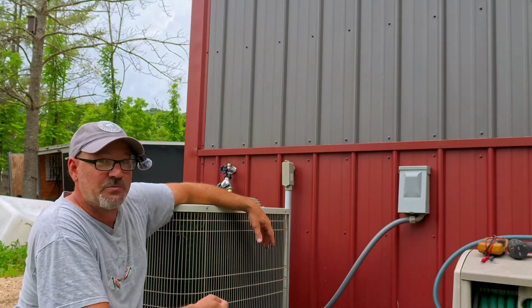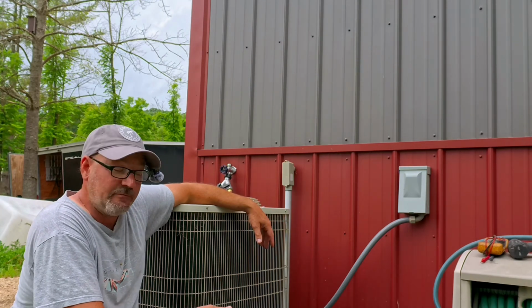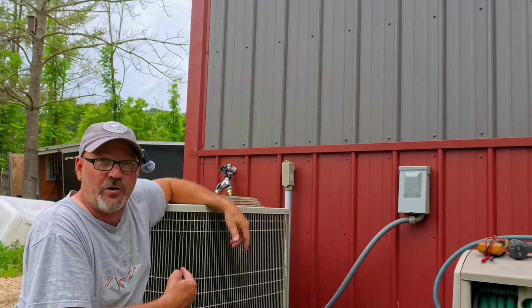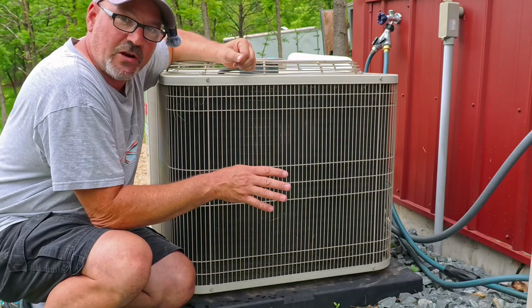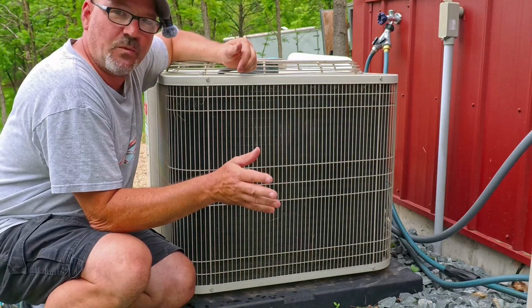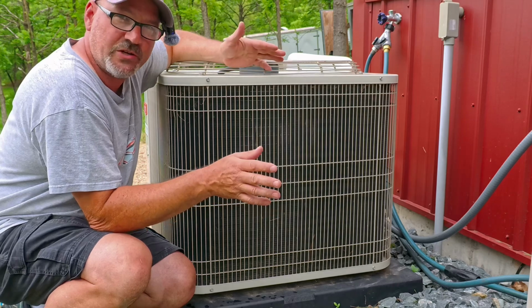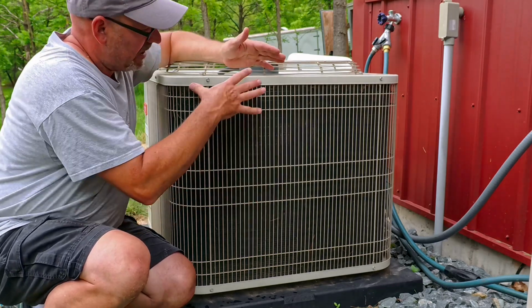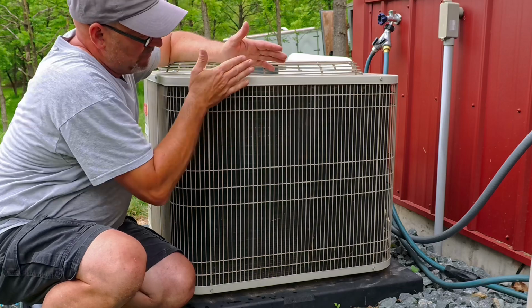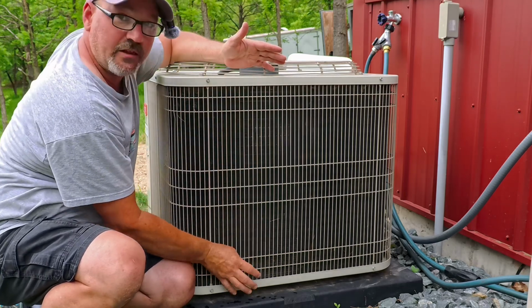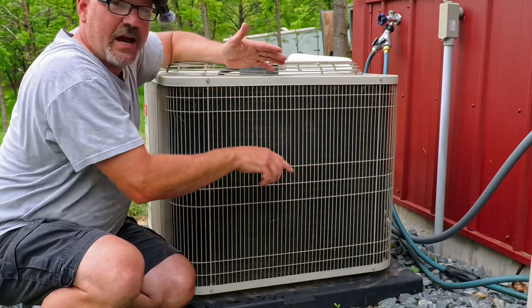You don't want to be spraying water into this unit when it's running. I understand it does get wet in the rain, but rain comes down on the system. It doesn't blow into the system. If you get this fan motor wet from the bottom, you're going to kill it. So after you shut the power off to the unit, it's very simple. Just take a water hose with a sprayer, medium pressure, don't get crazy, and all you have to do is go side to side, wash the unit down, get all the gunk to the bottom, and then try to spray it out the best you can.